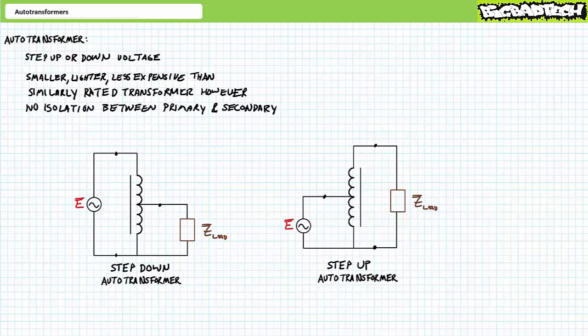An auto transformer is a special type of transformer with only one winding, and that single winding or portions of it serve as both primary and secondary. Like traditional transformers, auto transformers can step up or down applied voltage depending upon configuration. The principal advantage is that compared to a similarly rated traditional transformer, auto transformers are smaller, lighter, and less expensive. The disadvantage is that being constructed with a single winding, the primary and secondary are not electrically isolated, so an auto transformer cannot be used in applications requiring electrical isolation between systems.